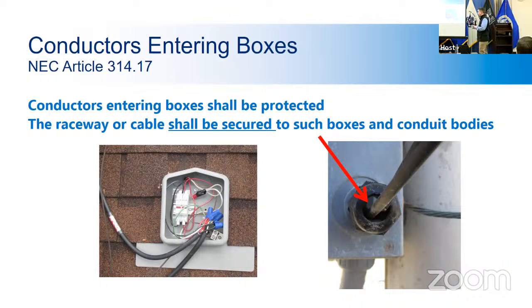And over here, you have several problems. The wire nuts used are not rated for outdoor use, even though this is in an enclosure. It's on a roof. It's going to be the same temperature and humidity as the outside air, so it's essentially an outdoor environment. And also, this contractor should have run the wires through one of the knockouts and used the fitting. Instead, they just tucked them up underneath the cover, which is obviously not optimal. So they would want to redo that. That makes it so you can't get a good seal on the cover, and it's out of code, right? You have to make sure that everything is installed correctly. Anyway.